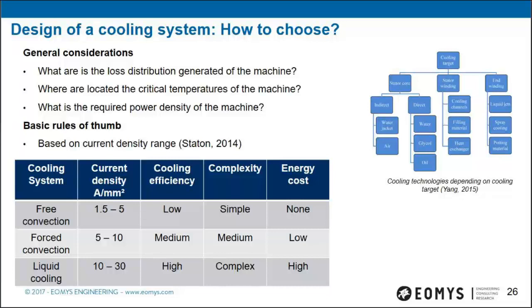How do you choose between all these architectures? There is no single answer, but key considerations include: where are the losses generated, where are the critical temperatures, and what power density is required? A basic rule-of-thumb table links cooling choice to current density: for low current density, free convection and totally enclosed machines suffice; for up to 5–10 A/mm², forced air convection is used; and for higher current density, liquid cooling is needed.